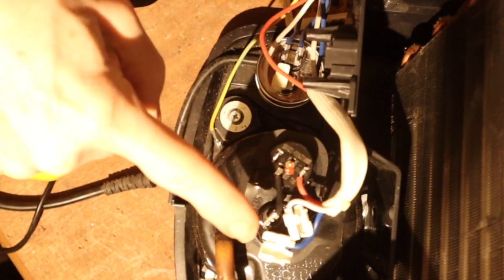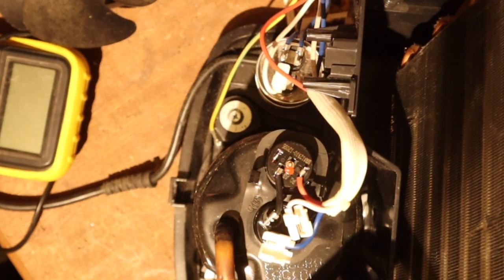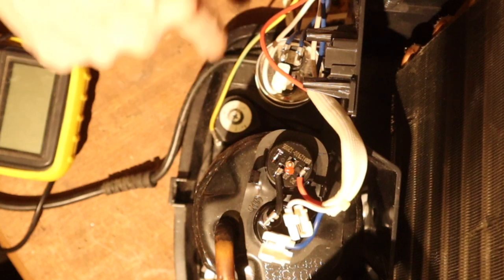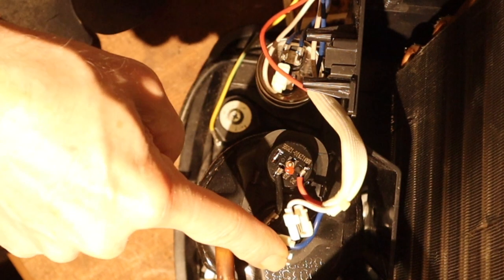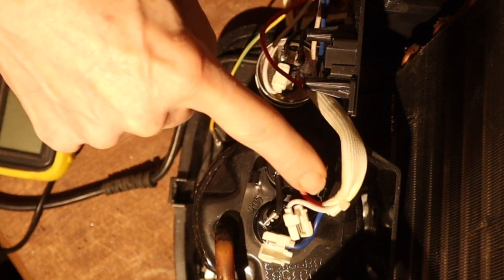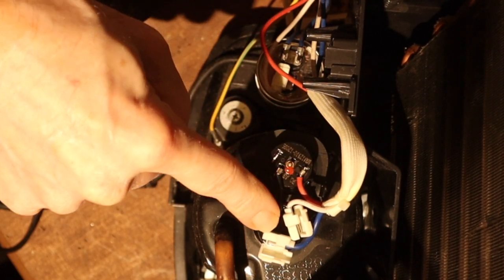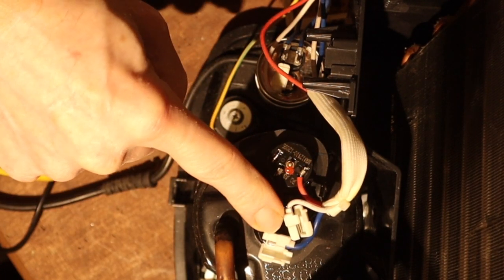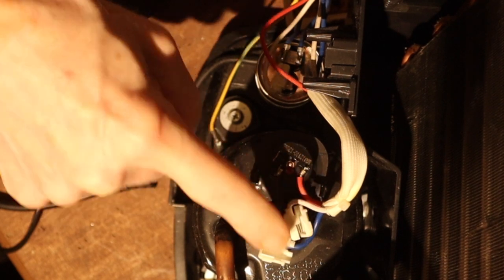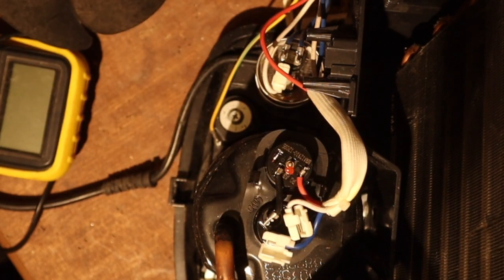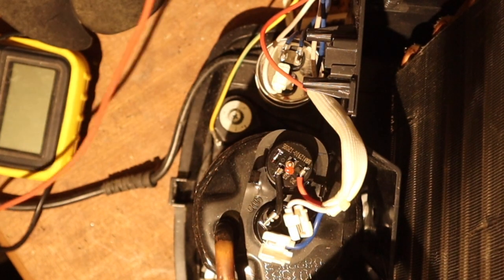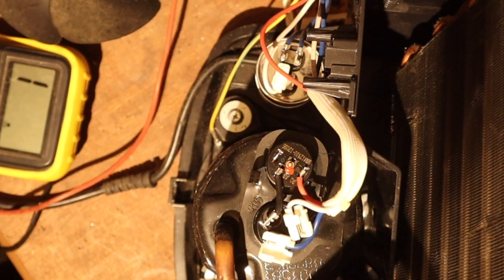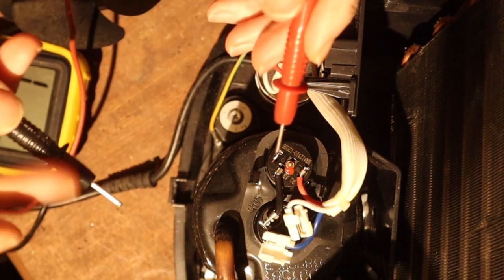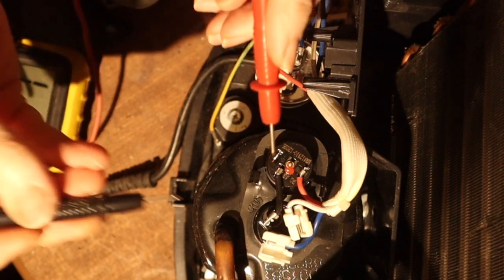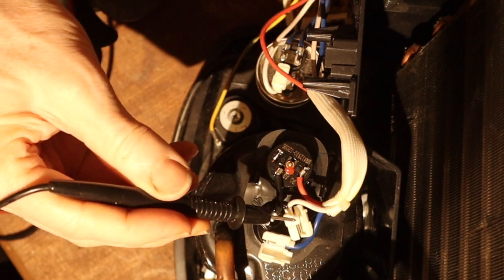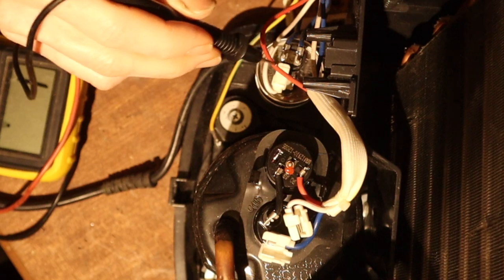But from the other side we see that this neutral blue color goes here, and here's coming the power, the red wire, and black becomes black and it's here. And then this must be the common, so the white is common. And if we make a resistance measurement, then we see indeed that the capacitor is connected between white and blue, as you see here.